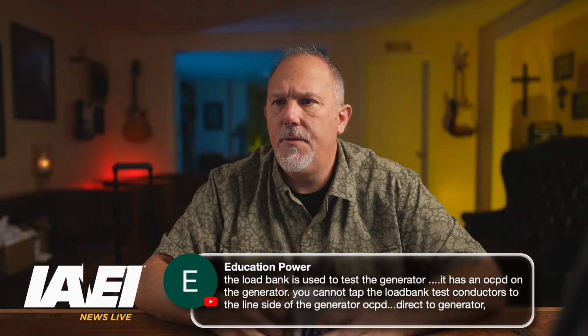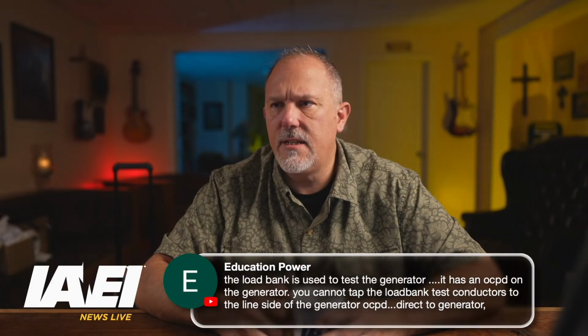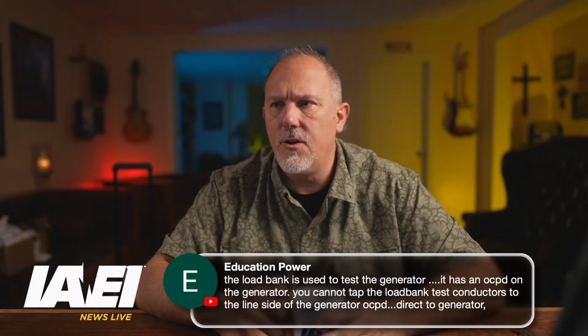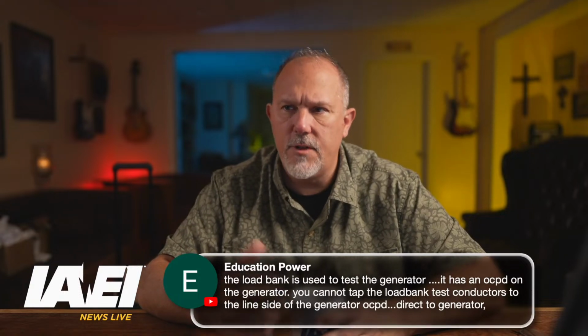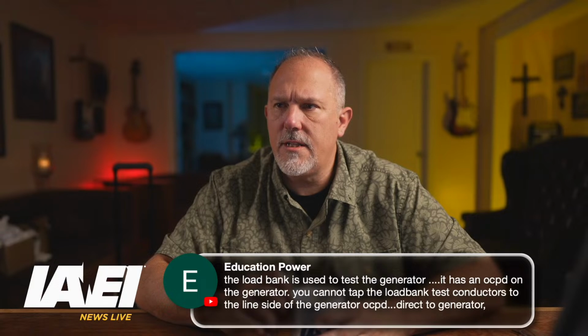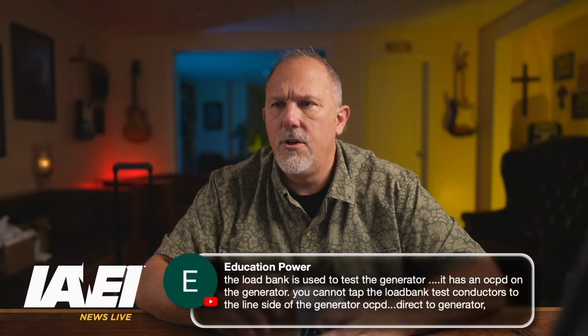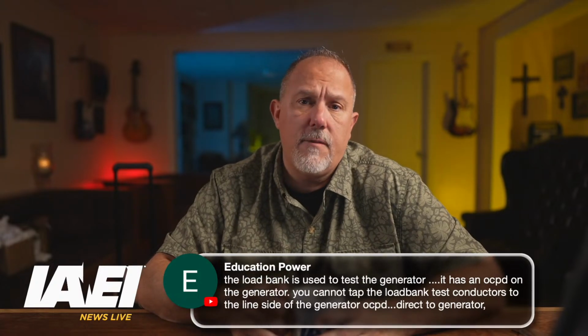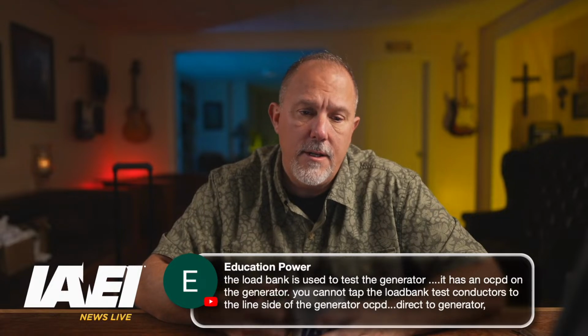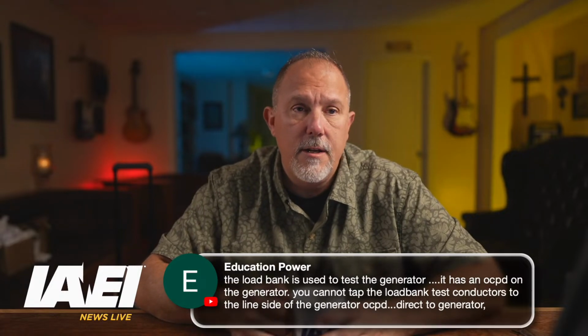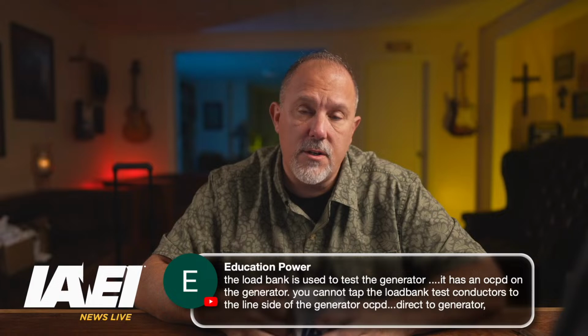Okay, we got a little bit more on this load bank. The load bank is used to test the generator. It has an OCPD on the generator, and you cannot tap the load bank test conductors to the line side of the generator OCPD, direct to the generator. So if you're testing the generator temporarily, that's a branch circuit.